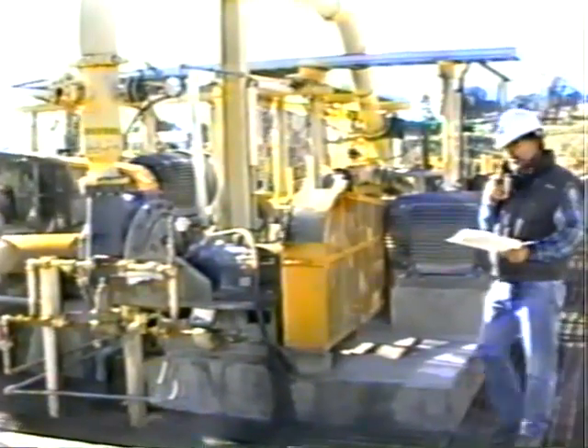In the GIW pumps, these are our booster pumps, which pump the material back up into our tailings basin. Currently, we're pumping at about 230 foot of head, and these variable speed units allow us to keep our pressures down and still get the material placed up in the tailings facility where we want to. These units, we're currently pumping with about 180 psi, and we're getting pretty good wear life out of these pumps because we're only running them at about 55% of max.